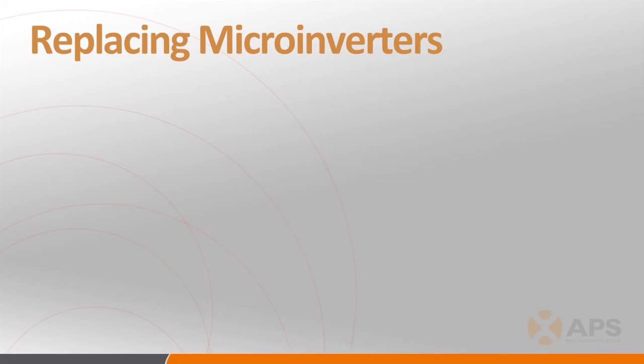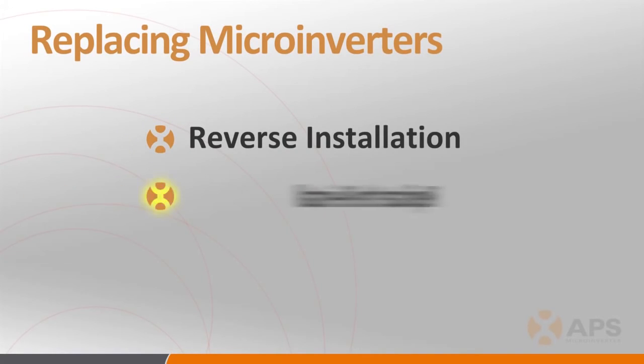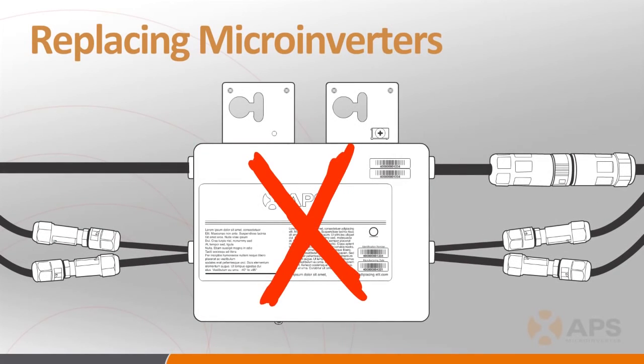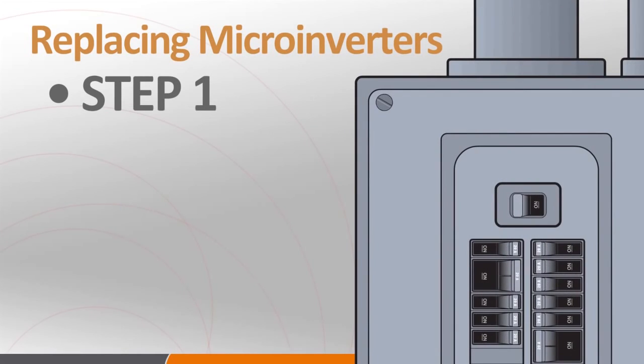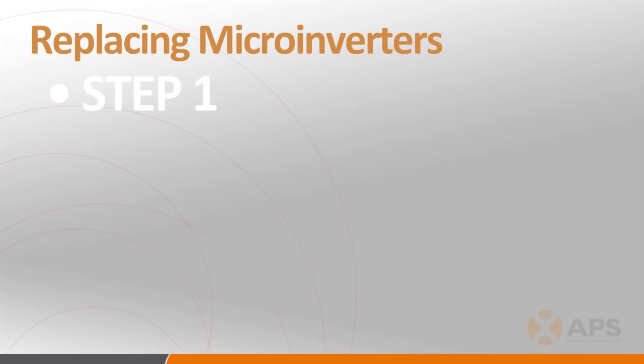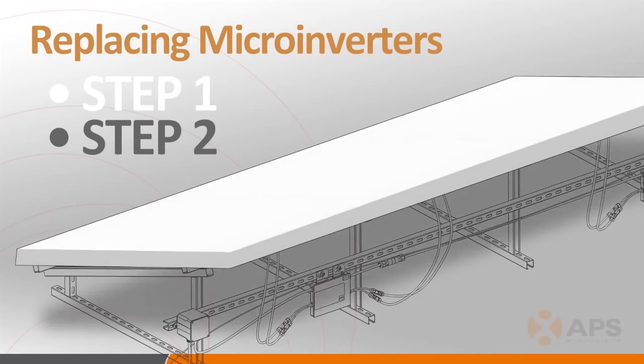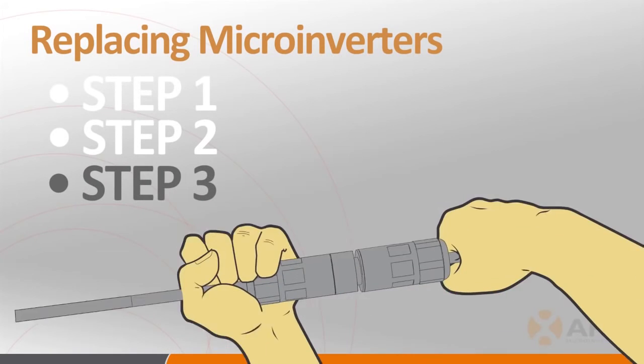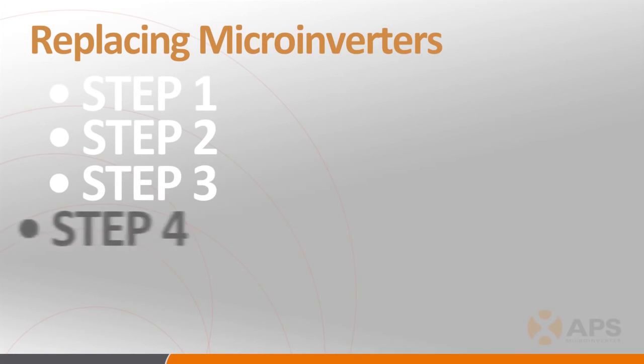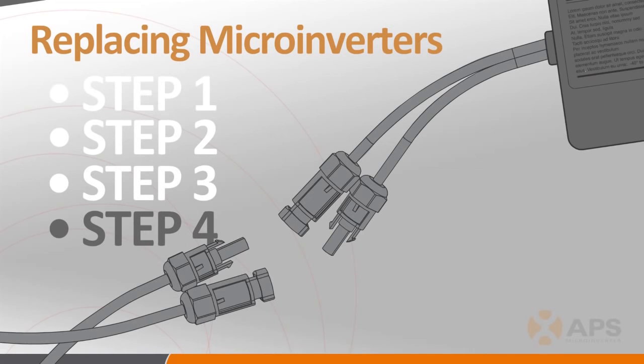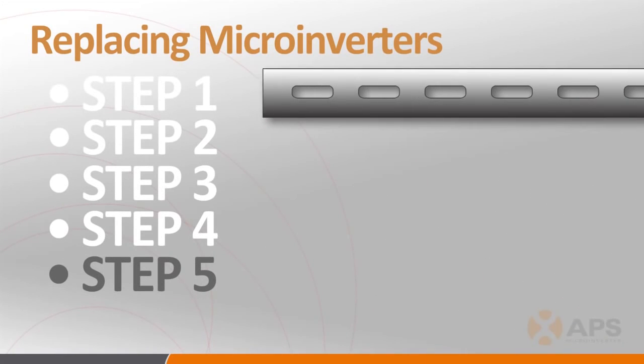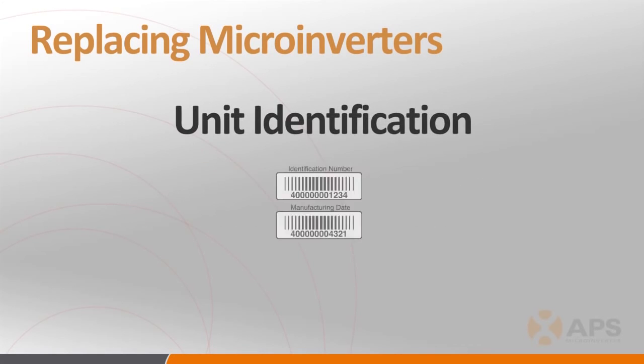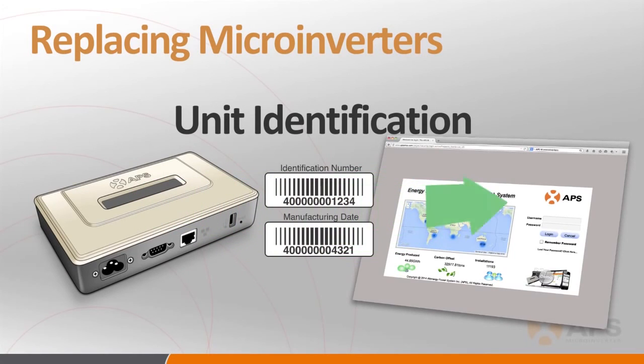Replacing the microinverters is as simple as reversing the installation process for removal and replicating it for reinstallation, with a few extra steps added for your safety. Step 1: de-energize the AC branch circuit by turning off the branch circuit breaker. With the branch circuit offline, cover the PV modules associated with the inverter to be removed with opaque covers, ensuring the panels are not producing DC power. Next, disconnect the AC connectors to the adjacent inverters. Step 4: disconnect the DC connectors from the PV modules associated with the inverter. And finally, physically remove the inverter from the rack. Follow the installation procedures covered earlier to install the replacement inverter, making sure to change the inverter UIDs in the ECU and EMA to reflect the changes you've made.